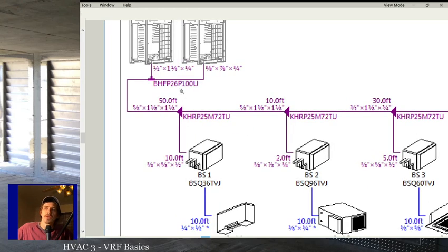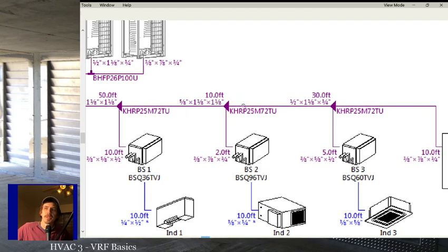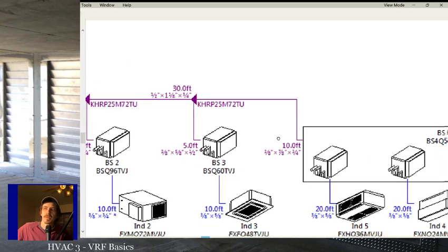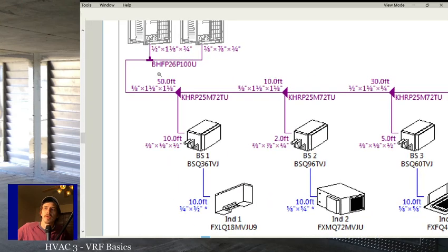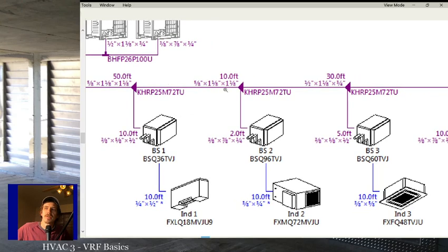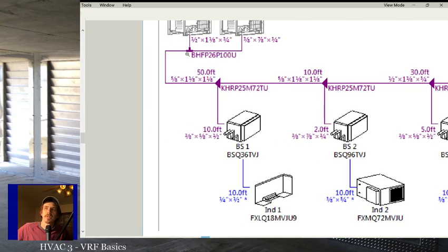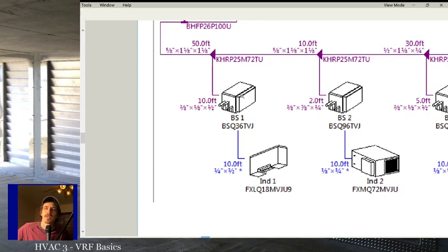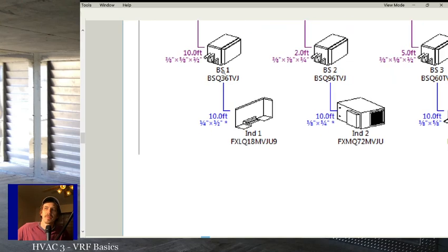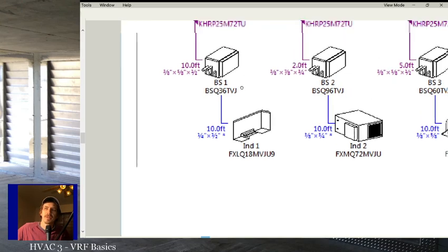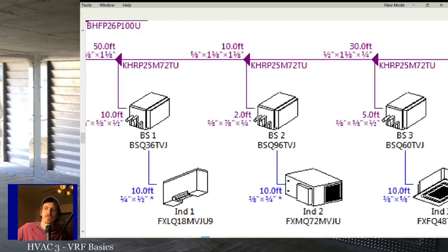So when you're installing these, especially if you're doing install only and you haven't taken many classes on them, like you're working under a guy that's taken a class, it's pretty important to make sure that you know the distances to each split on these units, no matter what manufacturer you're working with. You have to know the distance of each section of line set until it gets to another component. So from the outdoor unit to the first Y, how many feet of line set is that? From that Y to the branch selector, how many feet of line set is that? From that branch selector to the indoor unit, how many feet of line set is that? And so on and so forth.